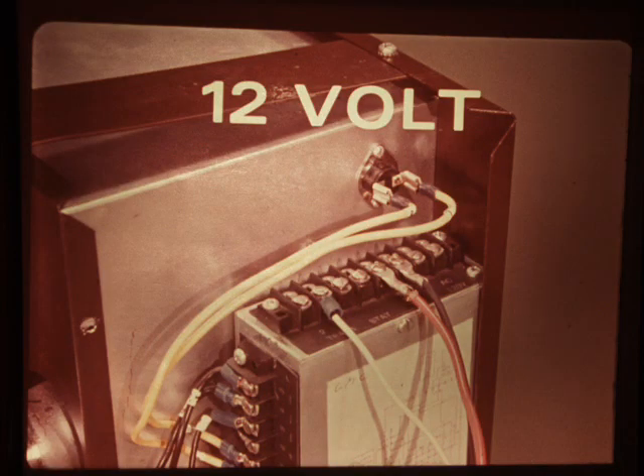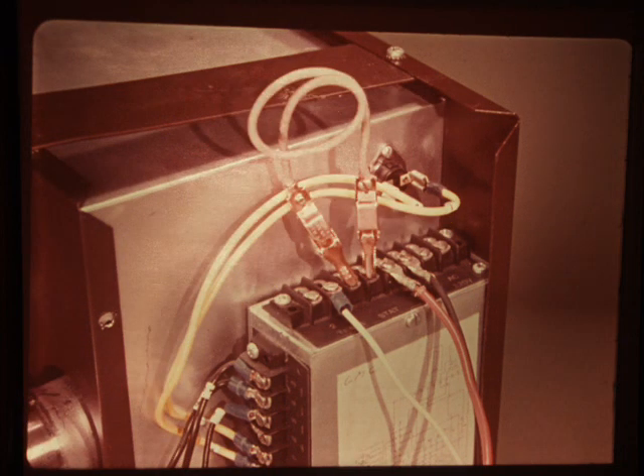On the bench, as we've done here, connect a 12-volt supply to the furnace power terminals on the control box. Use a jumper wire across the thermostat terminals to start and stop the furnace.